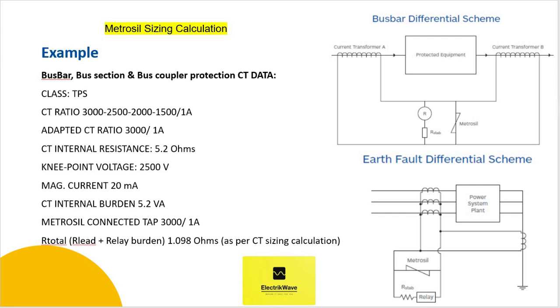We will consider bus bar, bus section and bus coupler protection CT data. Class TPS. CT ratio 3000-2500-2000-1500/1 ampere. Adapted CT ratio 3000/1 ampere. CT internal resistance 5.2 ohms. Knee point voltage 2500 volts. Magnetizing current 20 milliampere. CT internal burden 5.2 VA. Metrosil connected tap 3000/1A. R total, lead plus relay burden, is 1.098 ohms, as per CT sizing calculation.